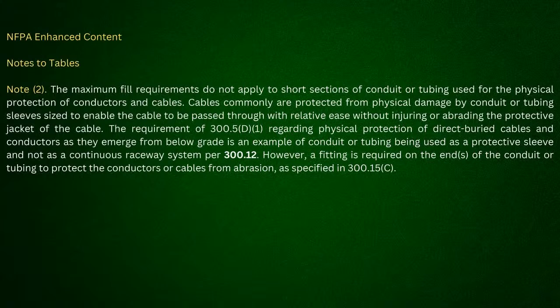Well, this goes back to what I was saying: you can go all through the NEC, and there are all kinds of places in there that talk about a sleeve. Yeah. And they don't give you a length on that either. Yeah, and what I'm saying is, when I'm looking at the NFPA Enhanced Content, and then I go look at 310.15(C)(1), it tells me it has to be a raceway. What are you going to do now? You're going to tell me a sleeve's a raceway and that the ampacity adjustment factors apply there? I just don't agree with that.